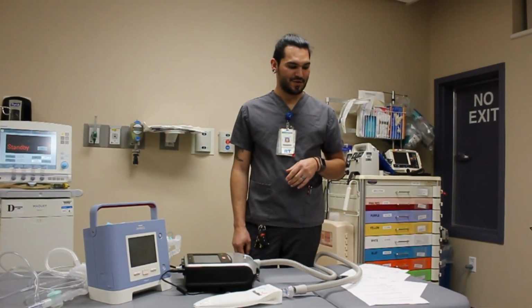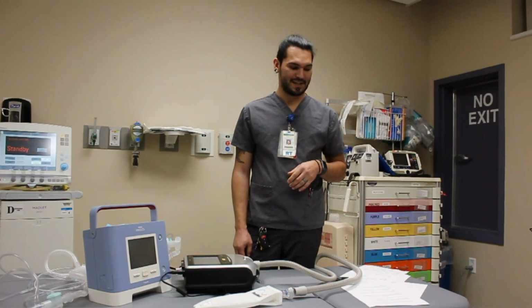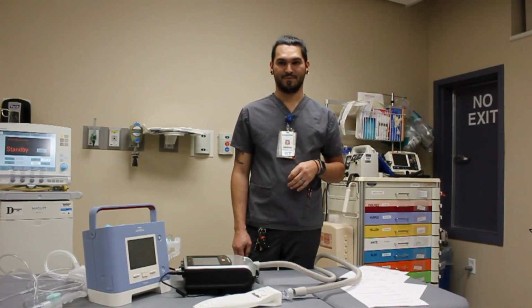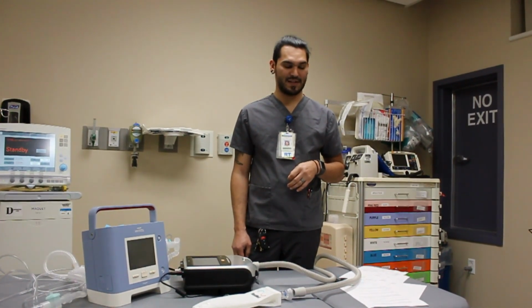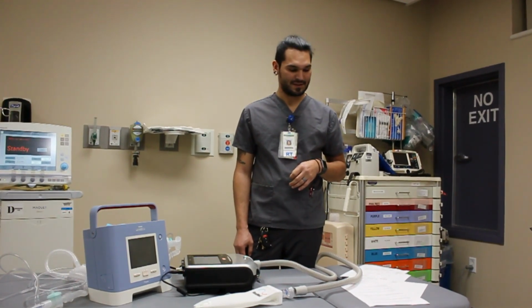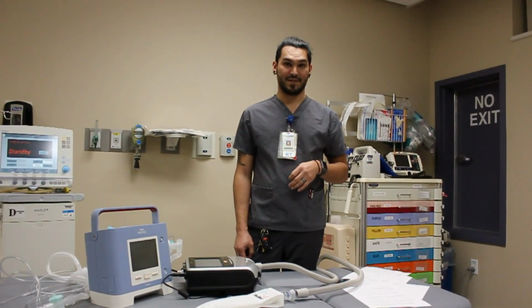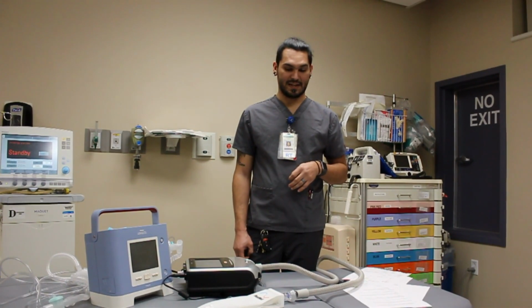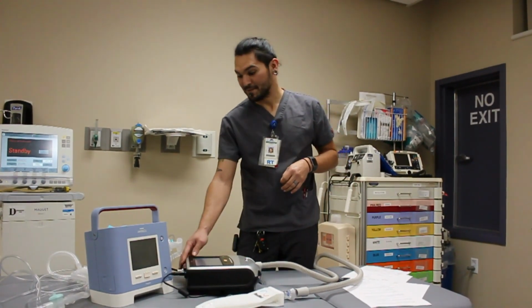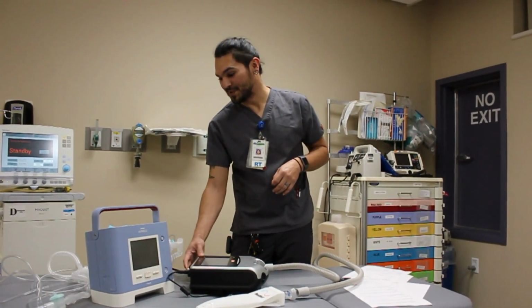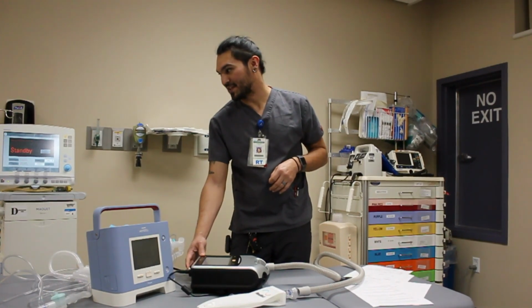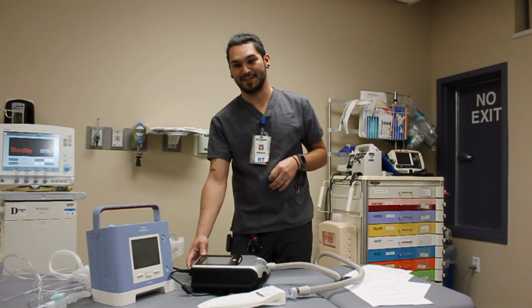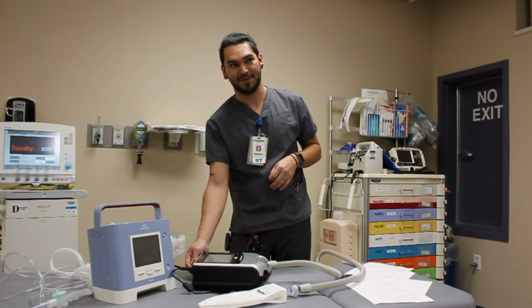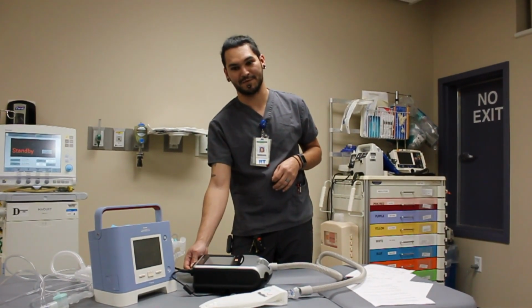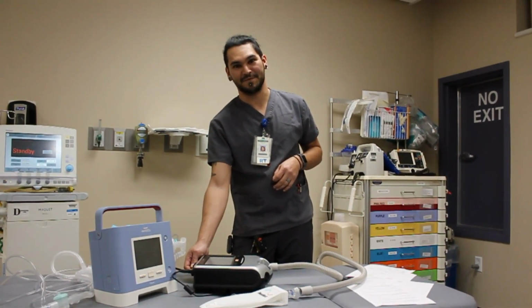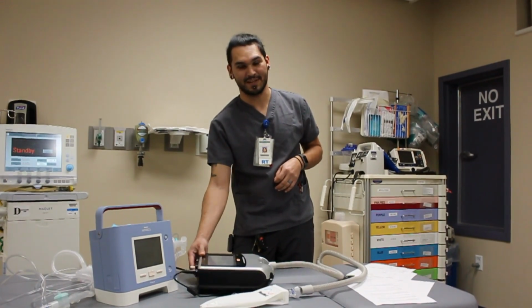Lastly, we can go over low sats. If your patient has a low sat alarm, we're going to check if the airway is in place and still patent. We're going to check for coughing and secretions. And it seems silly, but we're also going to check and make sure your O2 tubing is actually plugged into the vent and the wall. More often than not, it's very simple. The tubing just popped off and all of a sudden we're having a desat because we're not getting any oxygen. Easy fix for that would be to plug it back in and see if our sats go up.